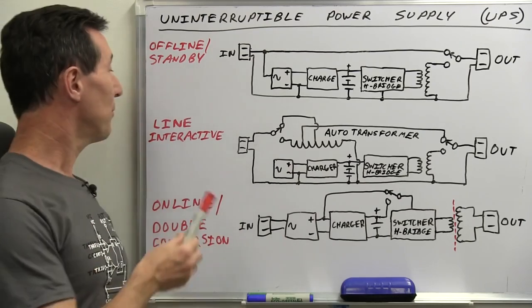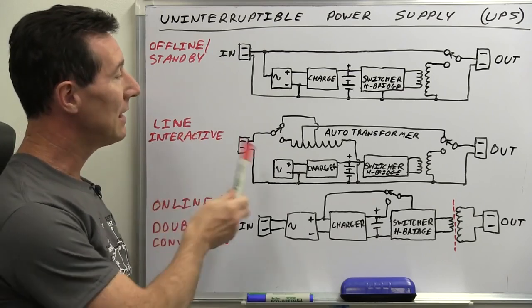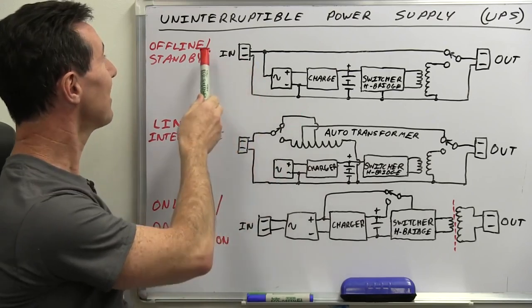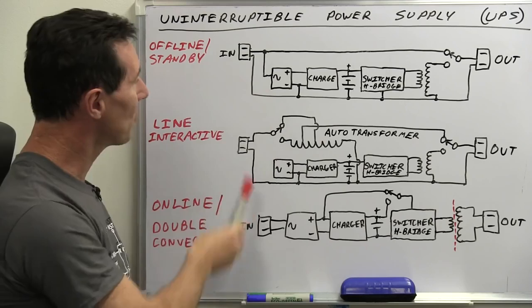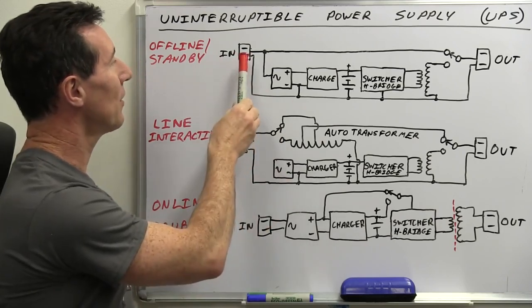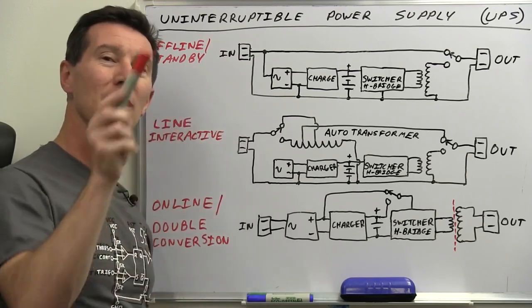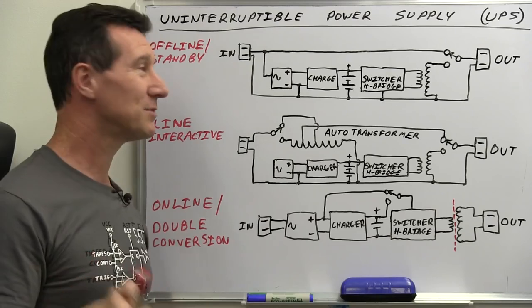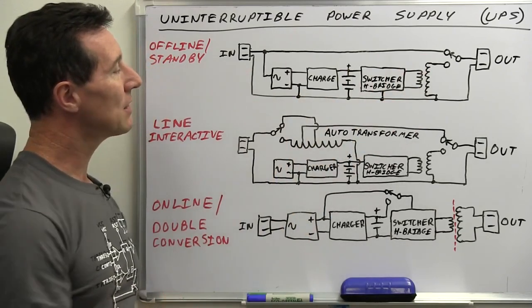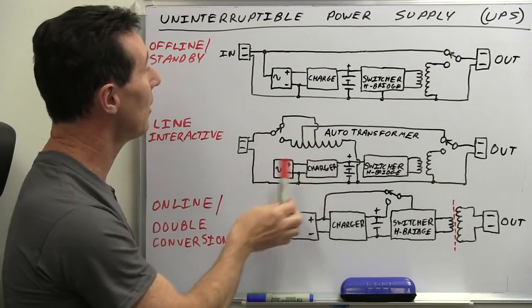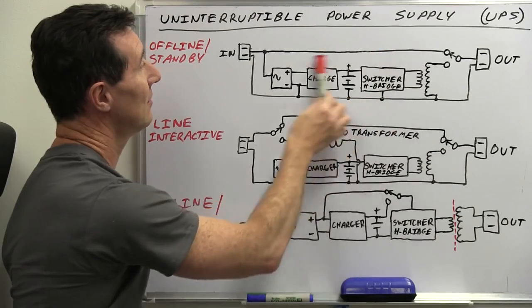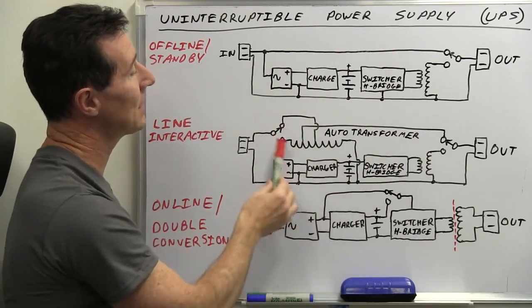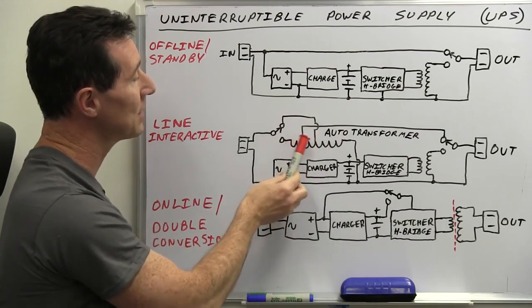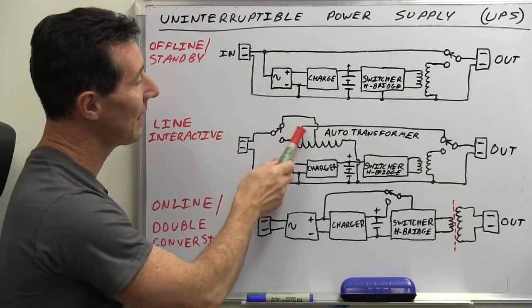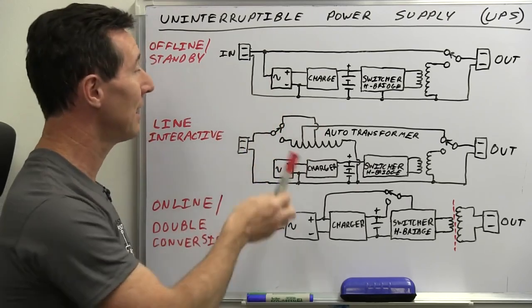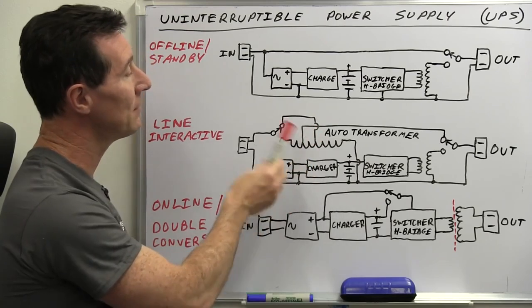So that brings us to the third type, which we're actually going to look at in the teardown today, what's called a line interactive UPS. And it's essentially exactly the same as the offline standby type, but it's a bit of a compromise between these two in that, let's say you've got a mains input here, which sort of browns out or drops out a couple of times a day. You don't want the thing always switching over to battery. So instead of it switching over to battery, what they include in here, you'll notice it's virtually identical, except for the fact that in this path here where the AC is switched through, there's actually what's called an auto transformer in there with various little taps with some other switching relays in here, or it doesn't have to be a relay, it can be an electronic switch as well. Then it switches between the different taps on the transformer.